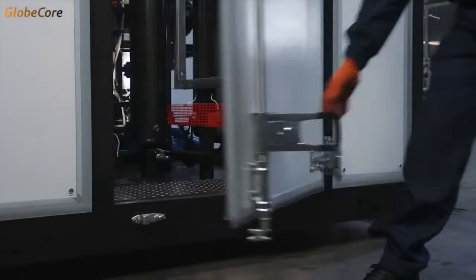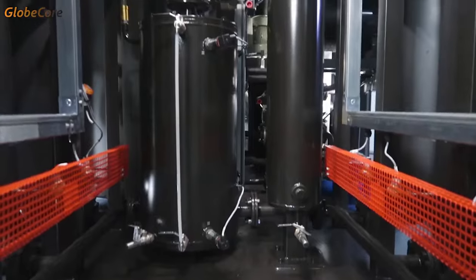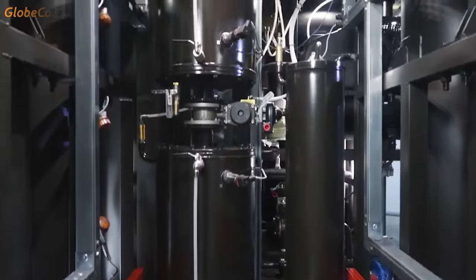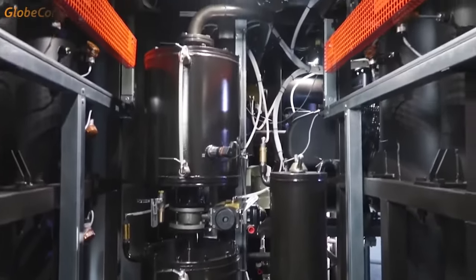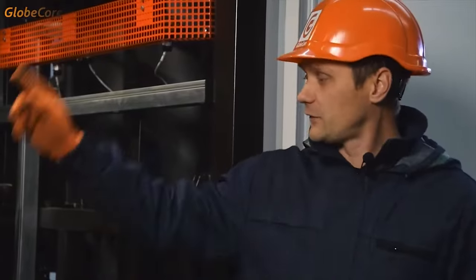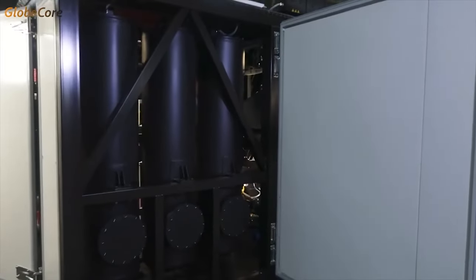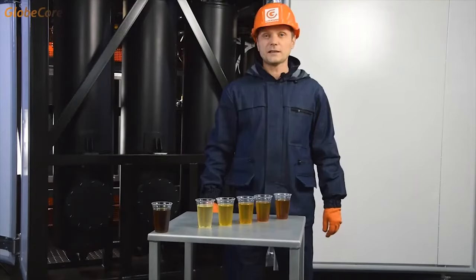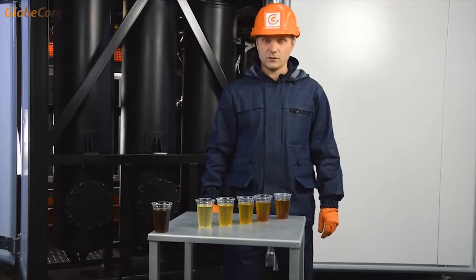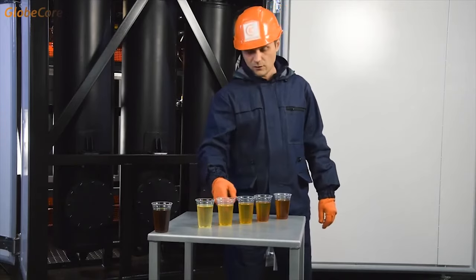Now let's take a closer look at how this process is implemented. In general, the basic principle of regeneration is the chemical interaction of the sorbent, specifically Fuller's earth, with oil. This is why the machine, in this case, is equipped with 6 regeneration columns, loaded with 150 kilograms of Fuller's earth each. This is where the oil is restored.